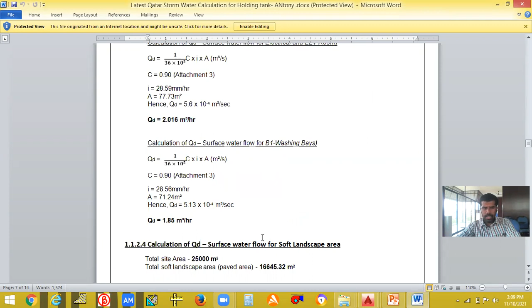Here I have calculated for both the surface water as well as the roof water. In total I got 260 meter cube per hour when I added all these things for the complete 8,354. So this is the consolidated sheet. This is the total area for roof. The discharge from this total area will be 216.69 meter cube per hour. So the holding tank capacity will be 487. How you got this 487 is that I have made this holding tank for 3 days.